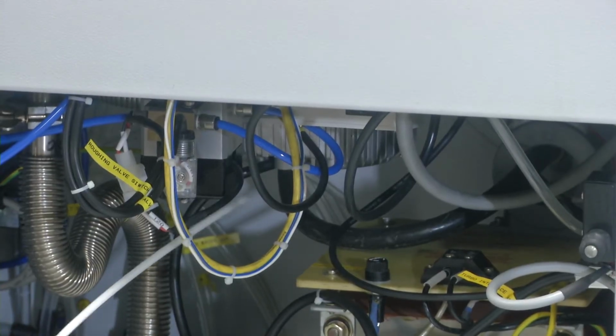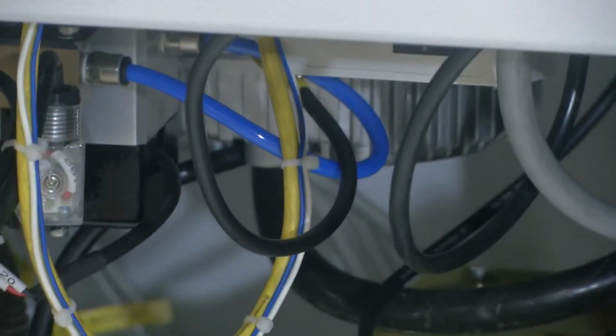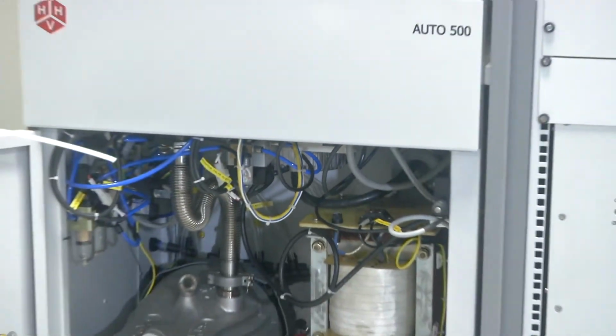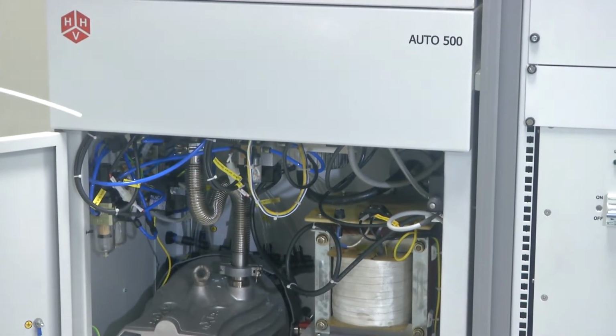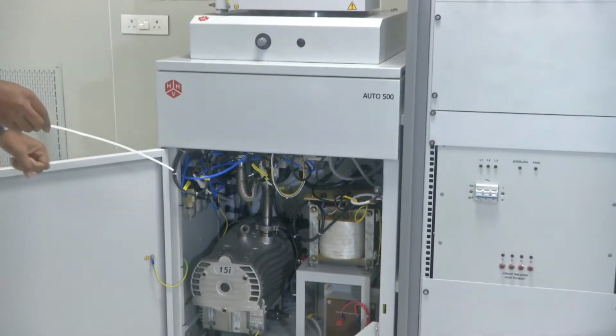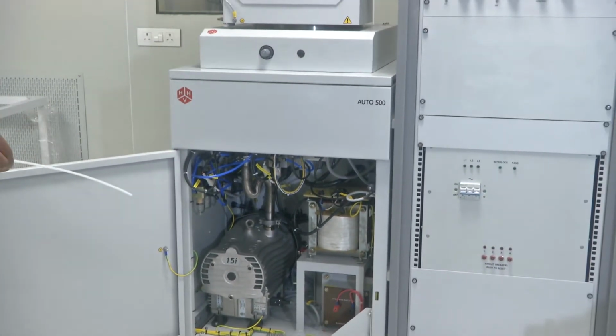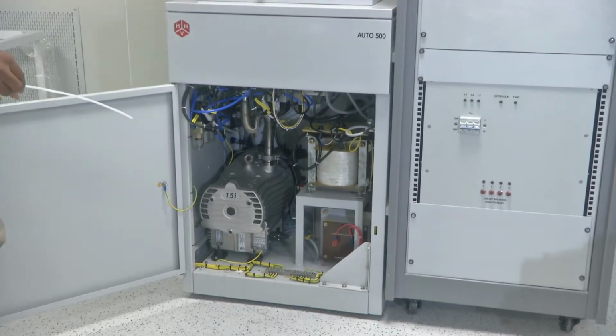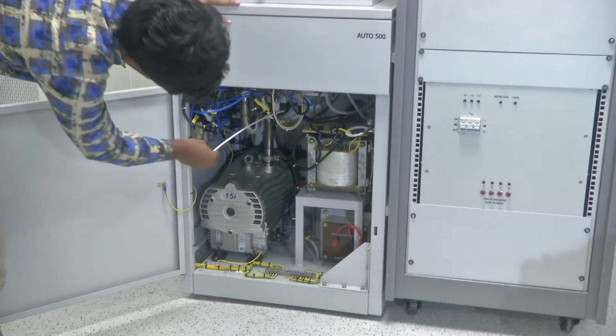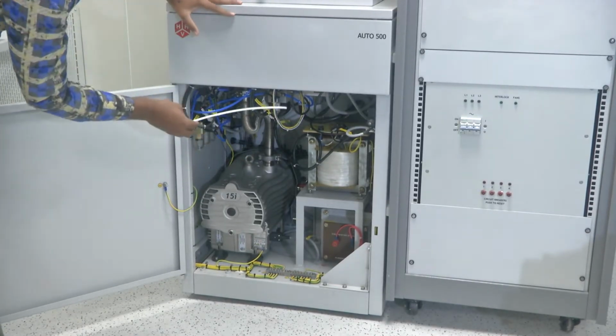After reaching roughing vacuum, we have to switch on the turbo pump. Then by using the turbo pump, we can move up to -6 and -7 vacuum levels. Size-wise, the roughing pump is bigger than the turbo pump. Turbo is fitted here. It's a turbo molecular pump, TMP.